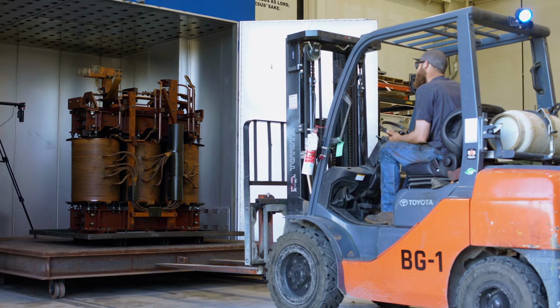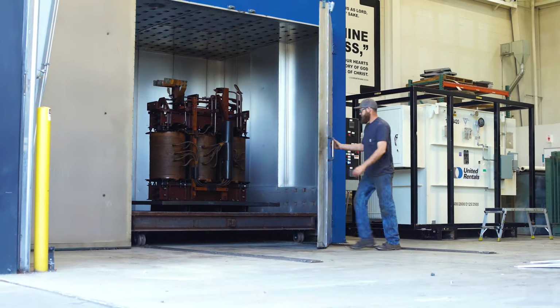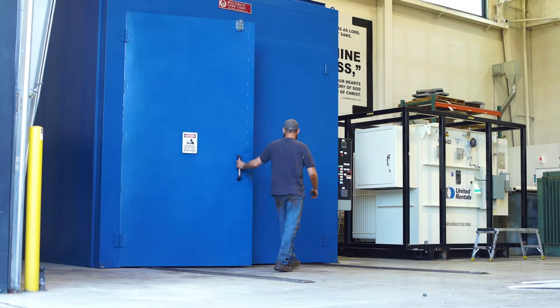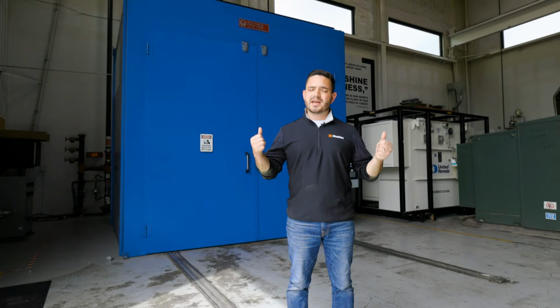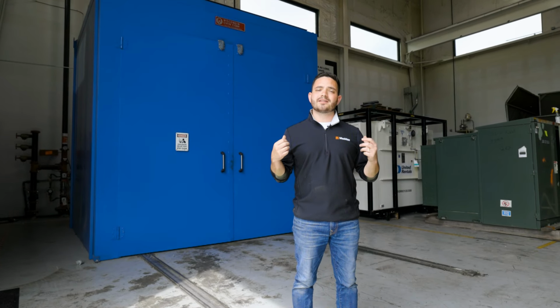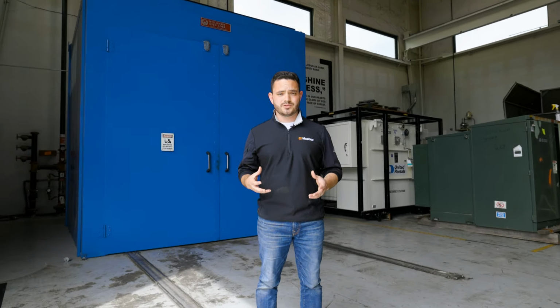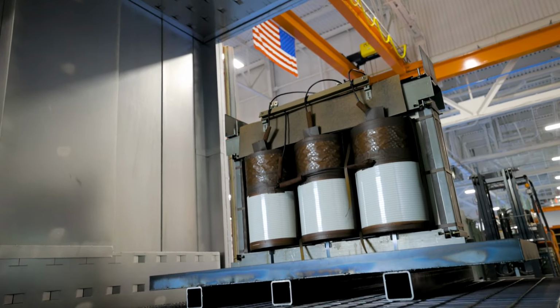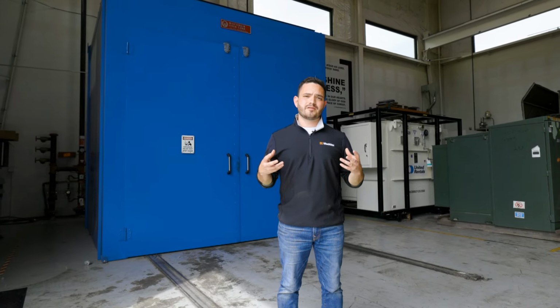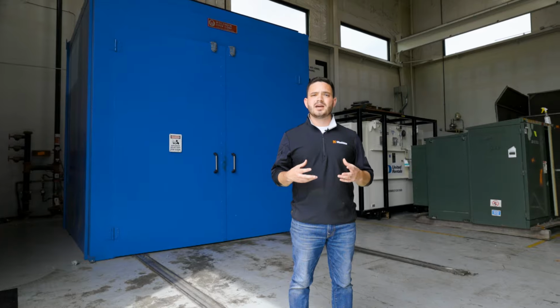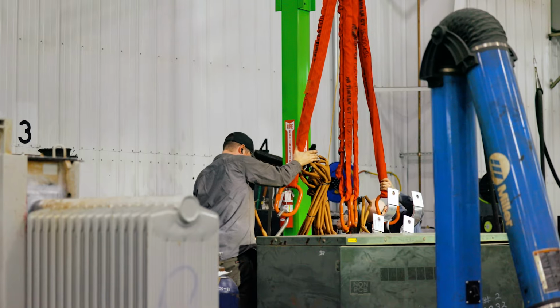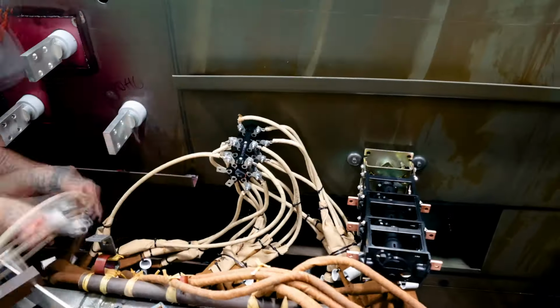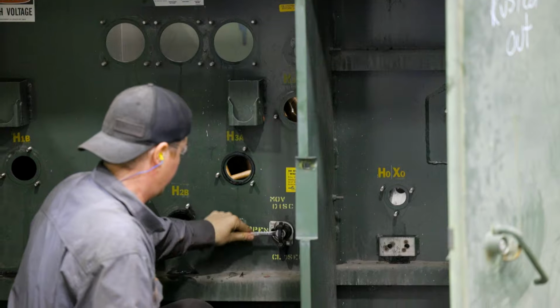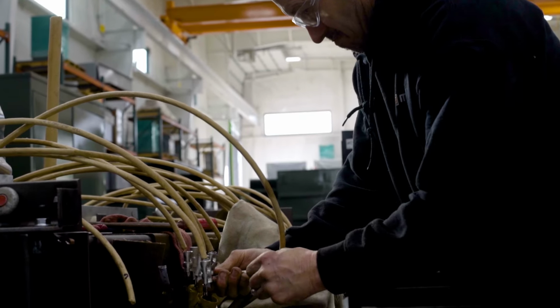But before we do, we need to bake it out. Otherwise, the insulation resistance will be poor because of the moisture in the environment. So we bake it out in this oven for several hours until we get an acceptable insulation resistance test result. Doing that also removes any combustible gas buildup that might have accumulated in the core and coil assembly in the transformer's previous life. Once the coil is back in the tank, our technicians reconnect everything inside. Most of the time, loose connections in these areas are what cause combustible gases in the first place. So ensuring a tight fit here solves 90% of the internal issues we come across.